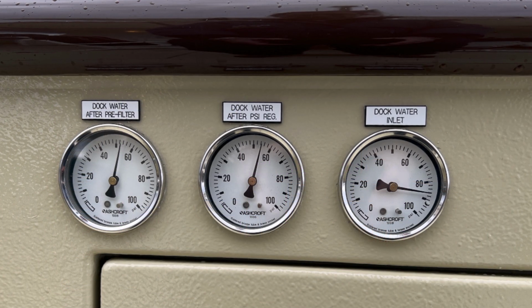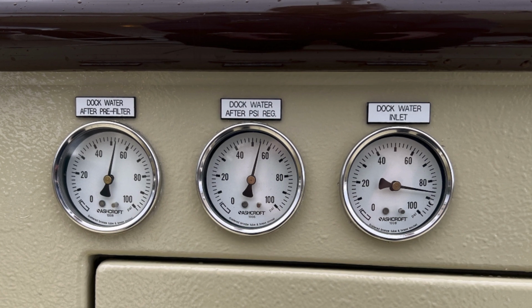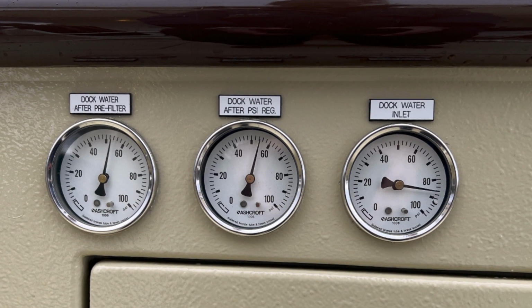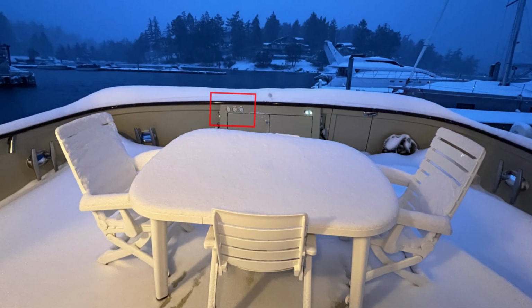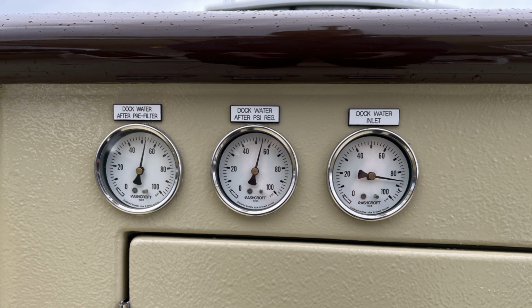The simplest, least expensive, and most reliable way to address these issues is with pressure gauges, which should be visible from the interior of the boat, plus a flow meter. To monitor this system, we measure the dock water pressure before the pressure regulator, again before it goes into the first pre-filter, and on the output side of the pre-filter.